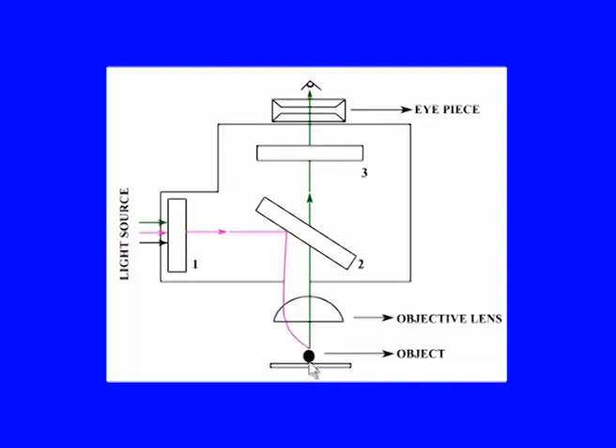The object is excited and emits a longer wavelength fluorescence, and that fluorescent wavelength passes through the dichroic mirror without any problem. It then passes through the second barrier filter, which allows only specific green fluorescence emission between 520 and 560 nanometers to pass through. Unwanted signals are cut here, and then the image can either be observed through the eyepiece or recorded. This is the typical optics of an epifluorescence microscope, where observation and emission are recorded from above.